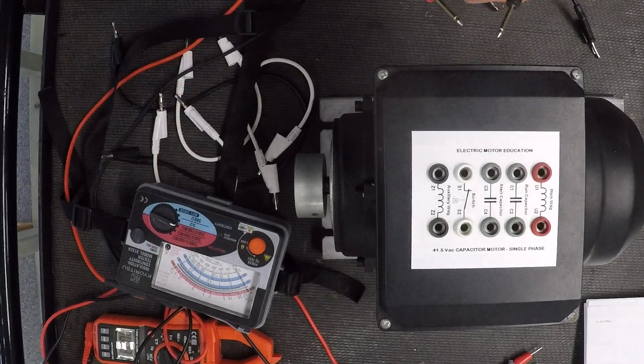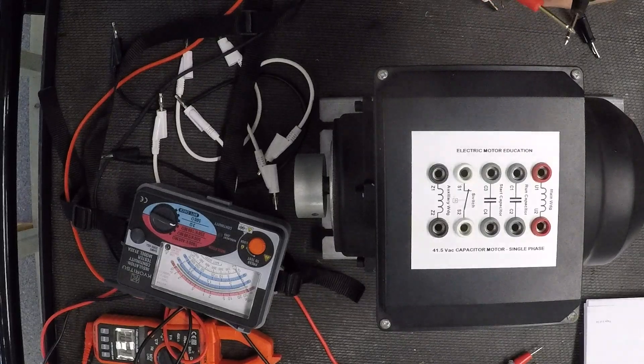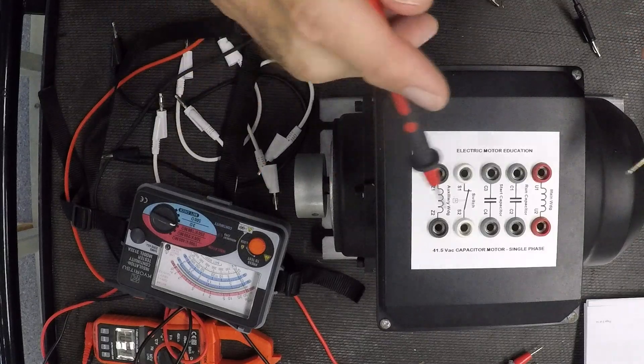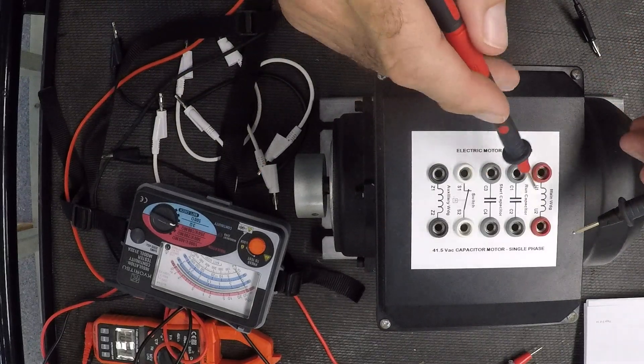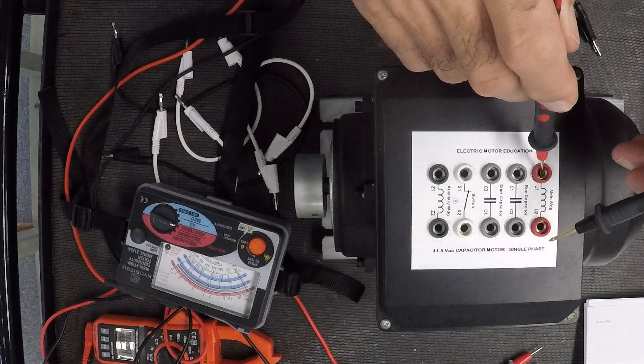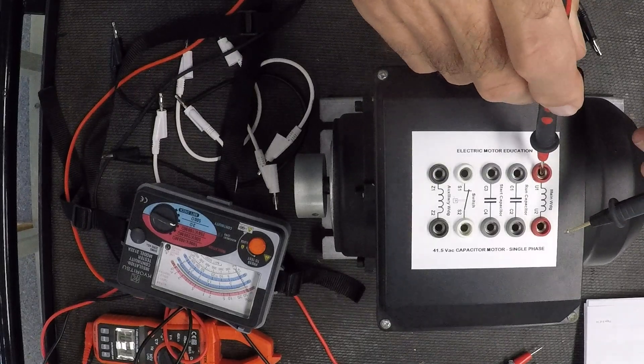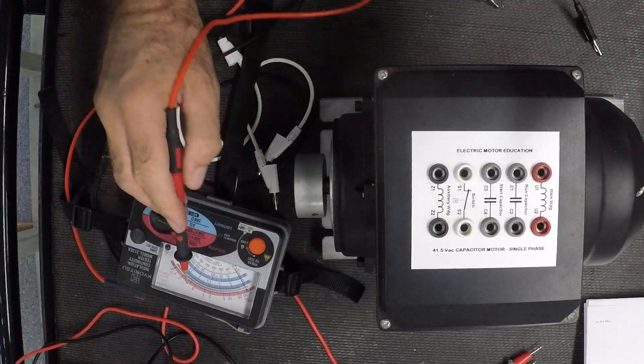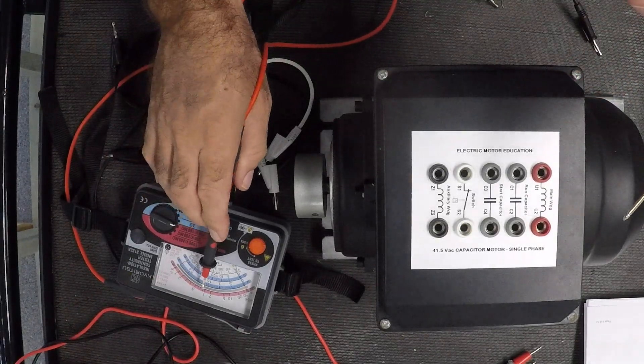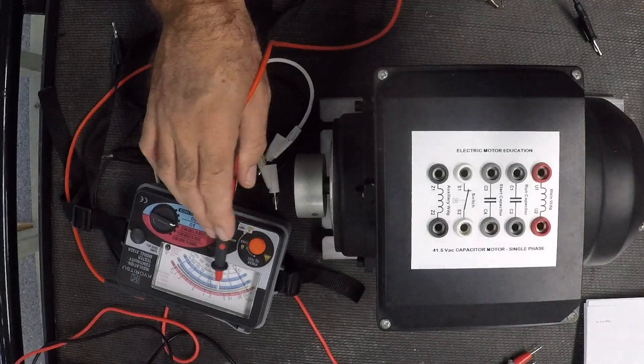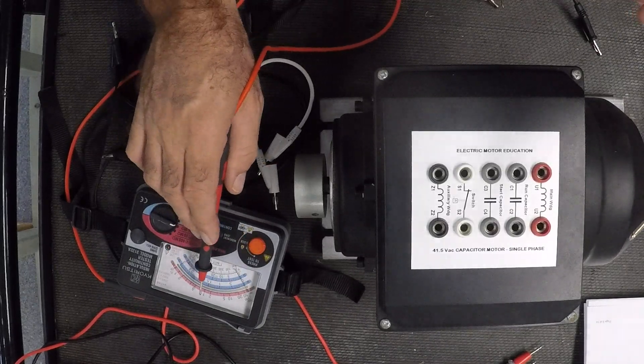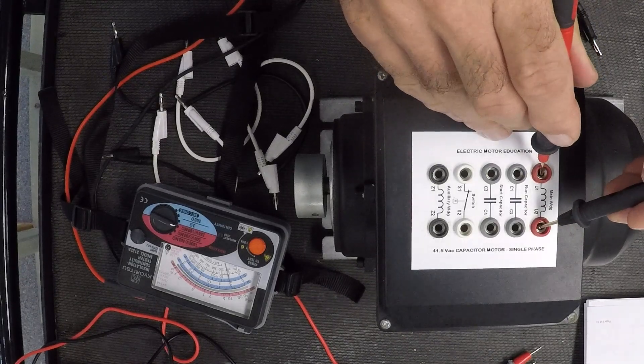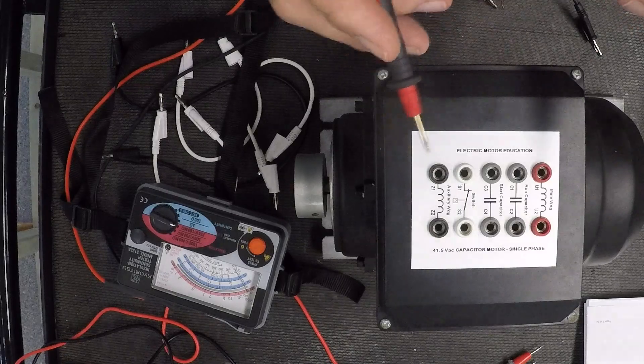Now I'm not going to go this way because if I do it, it's going to show me that there's a fault. When I do my IR, I want to get a reading that's greater than one megohm. You can see one megohm is over there, so it needs to be on this side, not this side, because that's zero. I'll show you if I make a mistake—see, that picks it up and shows me as a fault, but it's because I'm doing the reading incorrectly.